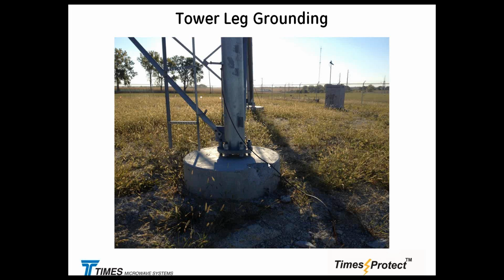So it looks like the impedance of that earth and the impedance of that whole structure was much lower than the impedance of that wire and that ground rod right here. And basically we have a flashover point, huge E-field build up, and the current said, I don't want to go this way, boom. And it took big chunks of the concrete right here. That's kind of like an oxymoron. What we are trying to protect from actually happened.